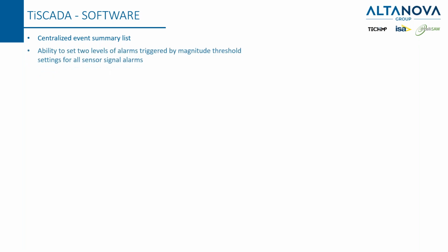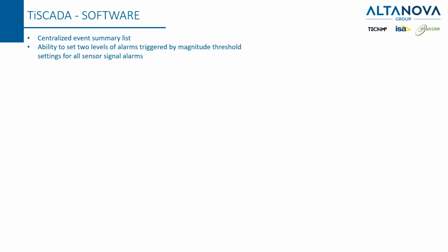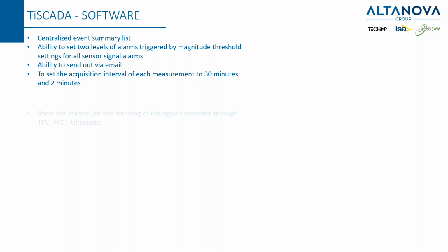The typical installation of the Falcon Mark II is for monitoring a large number of medium voltage panels, and requires the so-called TechImp SCADA, a software solution that is able to centralize the event summary list, and is able to set 2 levels of alarms by magnitude, threshold, etc. It is able to send out the alarm via mail, and to set the acquisition interval of each instrument from 30 minutes down to 2 minutes. This actually depends on the customer requirement.